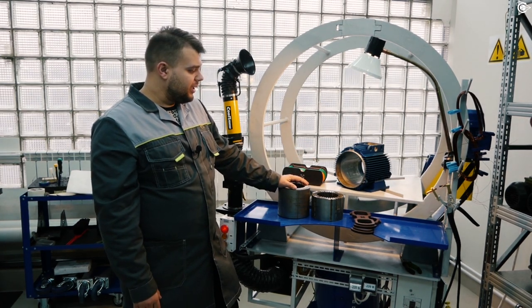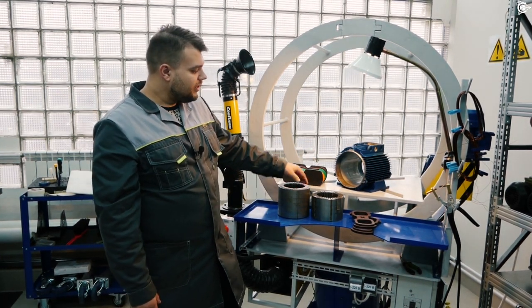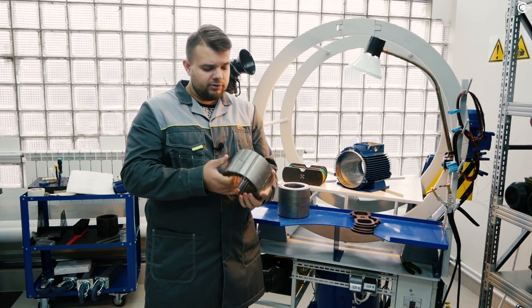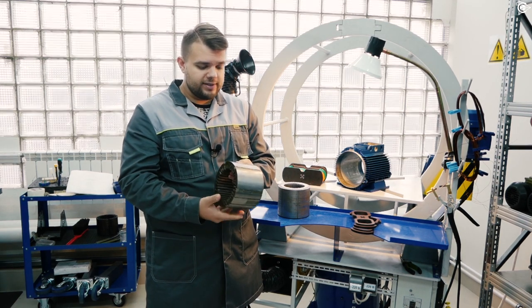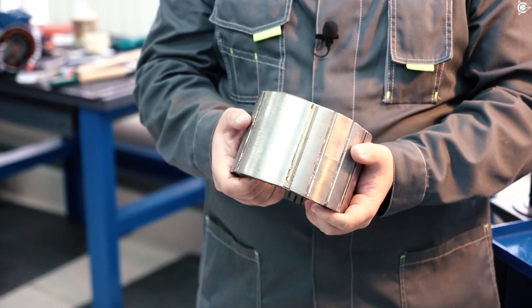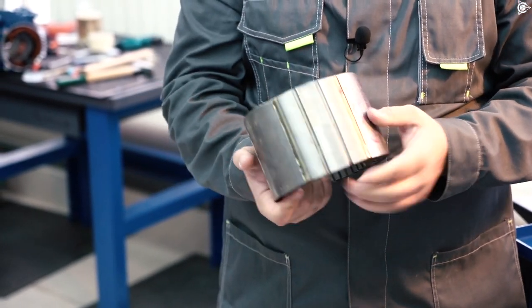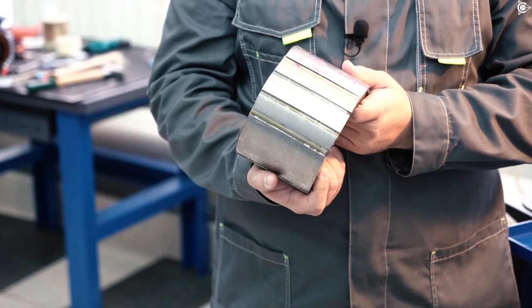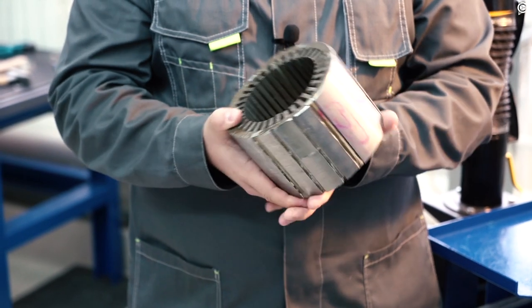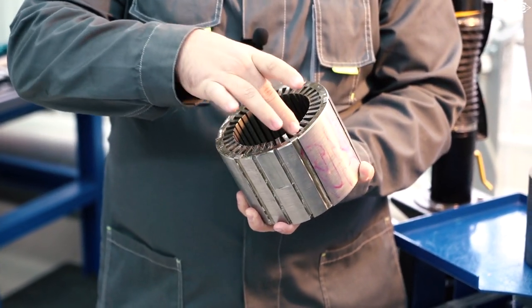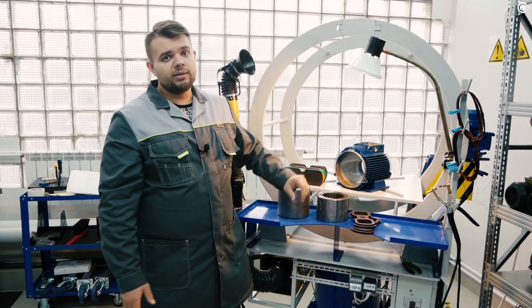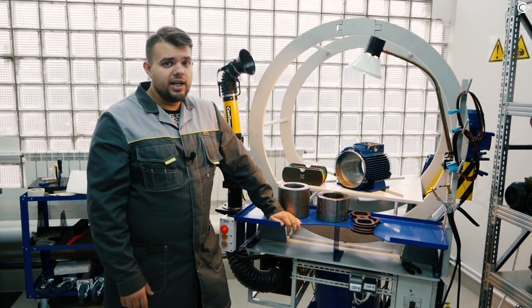This is a stator pack and the rotor pack. If we have a look at the standard stator pack, we can notice a lot of interesting details. First, we can see a large number of technological proofs that compromise integrity of the pack. And we also can see that the packs have been assembled by means of bracketing. In other words, it means that the packs are a bit indented and deformed. And this takes its toll on the future motor operational capability and affects its performance.